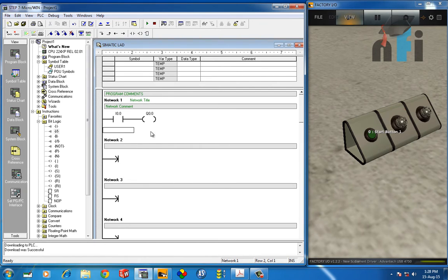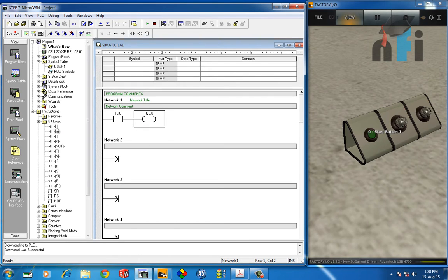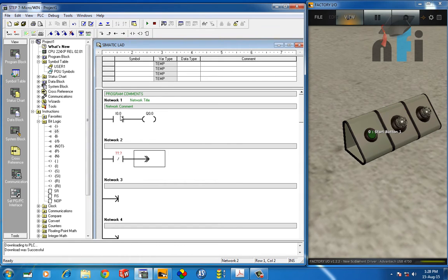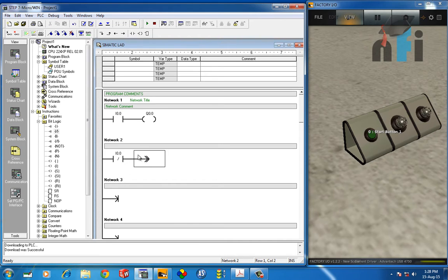In Siemens, when you are making logic in one network, you can only write one output or connect contacts in parallel or series. If you need another output, you must write it in a separate network — that is the principle. So I'll take an NC (normally closed) contact of I0.0 in the second network, since Q0.1 is the inverse of Q0.0, and assign it address Q0.1.